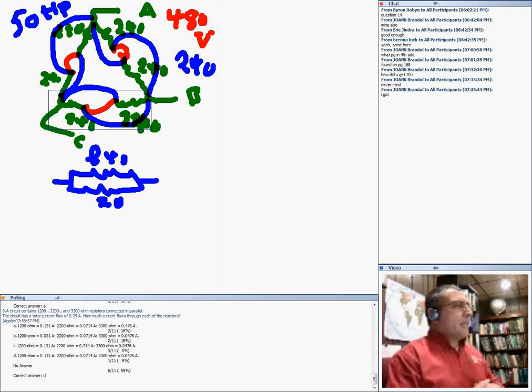It's going to be different in the amount of current it consumes - if it's 240, it's going to have more current; if it's 480, less current. Power, though, stays constant - the amount of power consumed from the system stays constant because the power rating is 50 horsepower. Think of it like carrying a 50-pound load in a bus or a 50-pound load in a car - you still achieve the same thing. The voltage is like the bus or the car. It's still a 50-pound load, a 50 horsepower motor, but to energize it you use different voltages because those are the voltages available in your system.